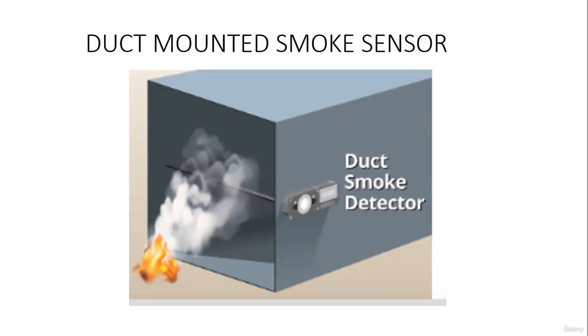I have a separate lecture series for ductwork takeoff, right? So there you can understand how to take off the ductworks and ducts. So now you can see here, this is the duct mounted smoke detector. When any fire happens in your ductwork, the duct smoke detectors detect the smoke. Then it closes your duct, right? It closes your duct. There is a fire damper, or sometimes smoke dampers are available in your duct, so it can be connected to actuators, and then it detects a fire, right?